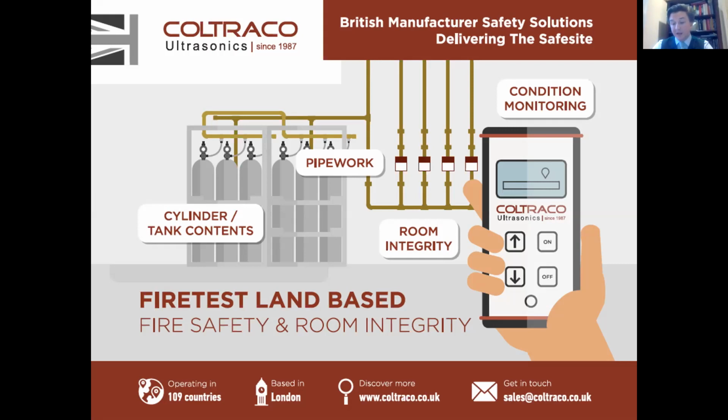Acoustic, where we do make equipment for bearing checkers. So many people are familiar with vibration units for checking the integrity of bearings in pumps, gearboxes, machinery, these sorts of things. Whereas acoustic is capable of identifying issues long before they become a vibration problem. Vibration is when issues have already occurred. Using acoustics, you can pick up the abrasion and the scraping of smaller issues before they exacerbate into full vibrations and major problems. So we do a lot of that with the shipping industry to look after, as I said, pumps, bearings, gearboxes, these sorts of things.